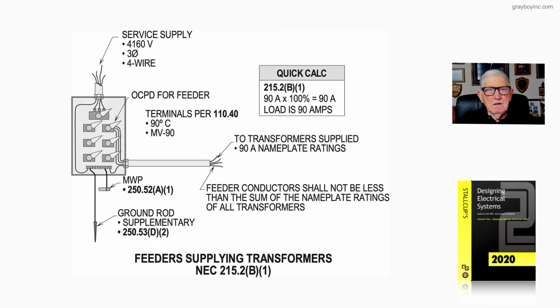Now, notice 110.14(C) deals with terminals at 1,000 volts or less mainly. But here we pick up 90 degrees C as your terminals for high voltage over 1,000 volts and 110.40, basically speaking. Then notice you have 100% loading. There's no derating in accordance with 230.208(B). When I say derating, if you had, say, a 100 amp overcurrent device in that switchgear there, panel board, whatever it may be, you wouldn't take 100 times 80% and just load to 80 amps. You could load those conductors to 100%.